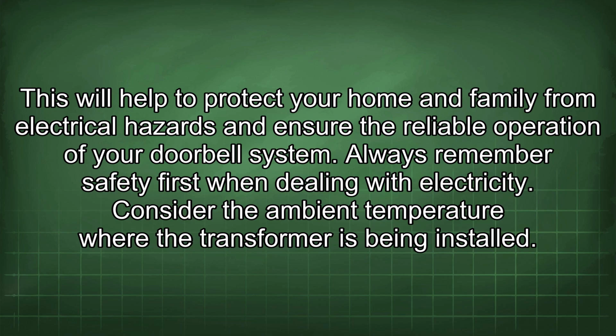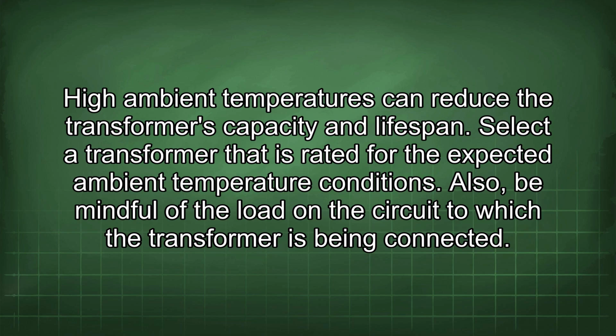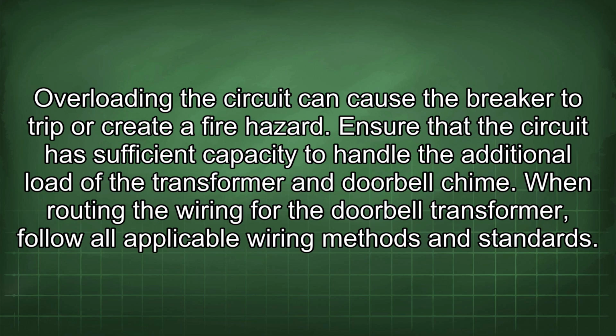Consider the ambient temperature where the transformer is being installed. High ambient temperatures can reduce the transformer's capacity and lifespan. Select a transformer that is rated for the expected ambient temperature conditions. Also, be mindful of the load in the circuit to which the transformer is being connected. Overloading the circuit can cause the breaker to trip or create a fire hazard. Ensure that the circuit has sufficient capacity to handle the additional load of the transformer and doorbell chime.